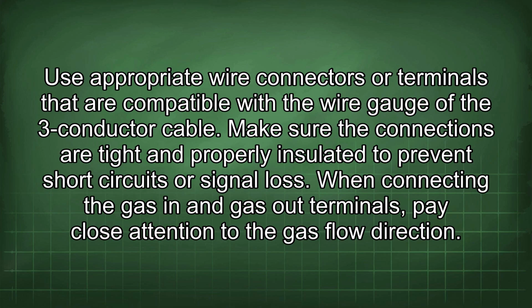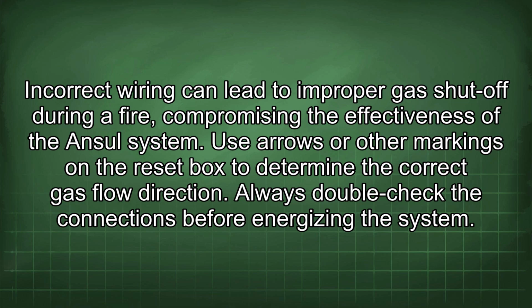When connecting the gas in and gas out terminals, pay close attention to the gas flow direction. Incorrect wiring can lead to improper gas shut-off during a fire, compromising the effectiveness of the Ansul system. Use arrows or other markings on the reset box to determine the correct gas flow direction. Always double-check the connections before energizing the system.